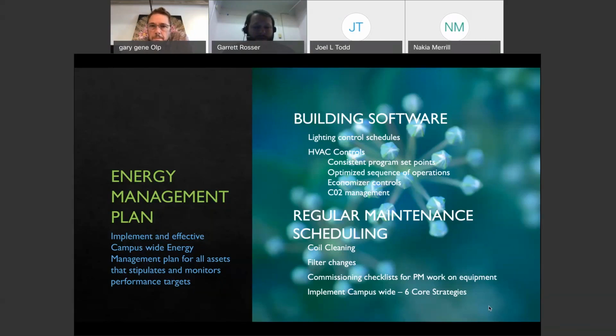And CO2 management, again, that's just making sure that your CO2 sensors are in good shape. And then you have great set points. There's some misunderstanding of ASHRAE Standard 62, and that is 700 parts per million above the baseline CO2 level is where your set point ought to be. So for us here in Dallas, that's somewhere in the 1,100 to 1,200 parts per million. If you wanted to run it at 1,000, I don't think you'd get too much argument from me. But 1,100 to 1,200 parts per million on CO2 is a great starting point there.